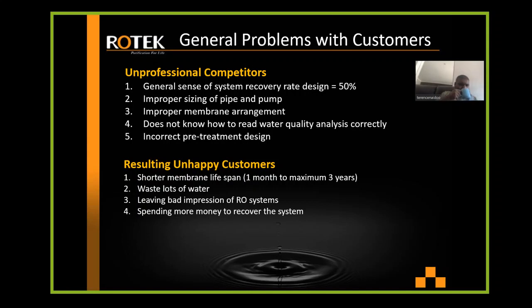So the water quality analysis that we get should exactly match the requirements, so that we are able to guarantee the customer how much recovery rate the system can be designed for. This is not just guessing, but something we can calculate scientifically from Avista software. But it also depends on the brand of membrane. Yes, but it doesn't make much of a difference.